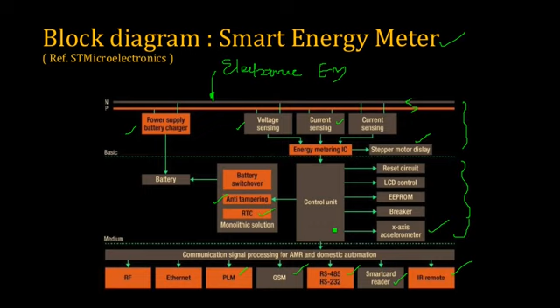Then you have a smart card reader, and some SIM cards will be provided. That SIM card will be operating as a communication medium. Such smart meters are also available. Then you'll have infrared remotes. All these things are available in a communication system, and when you incorporate everything together, you get a smart energy meter. The only difference between a smart energy meter and an electronic energy meter is that along with the recording part, you have a communication part available, which communicates between the energy meter and different stakeholders.